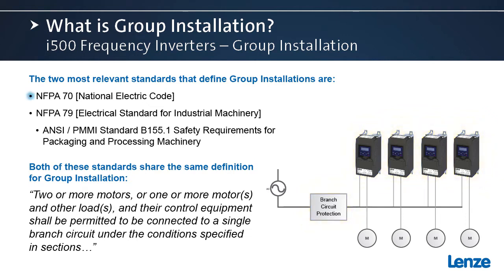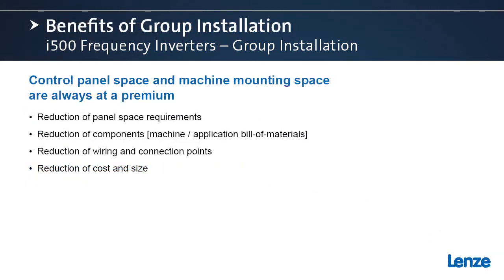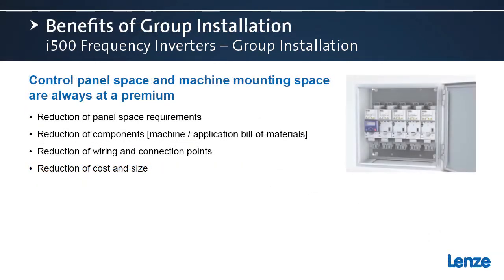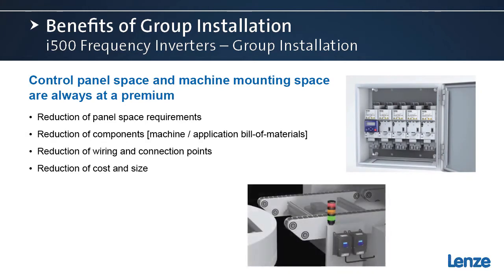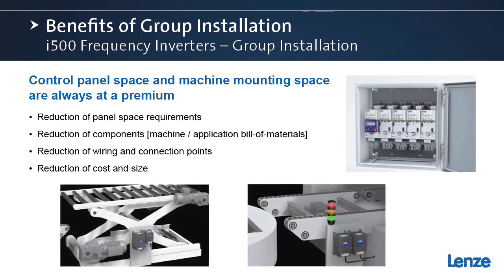NFPA 70, the National Electric Code, and NFPA 79, the Electrical Standard for Industrial Machinery, both have guidelines and requirements for applying group installation techniques. Both the NFPA 70 and the NFPA 79 are recognized and actually referenced by the ANSI PMMI standard, the safety requirements for packaging and processing machinery. Applying the guidelines in the standards to accomplish group installation permit the reduction of the number of branch circuit protectors that may be required on the machine.